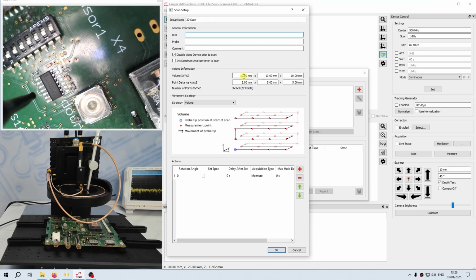Then it's time to define our volume. We can set up the size of the volume in X, Y, and Z direction, and the distance of each point to the next one. So for example, we set up a measurement volume of 10 millimeters by 10 millimeters by 5 millimeters with a distance of 1 millimeter between each point.